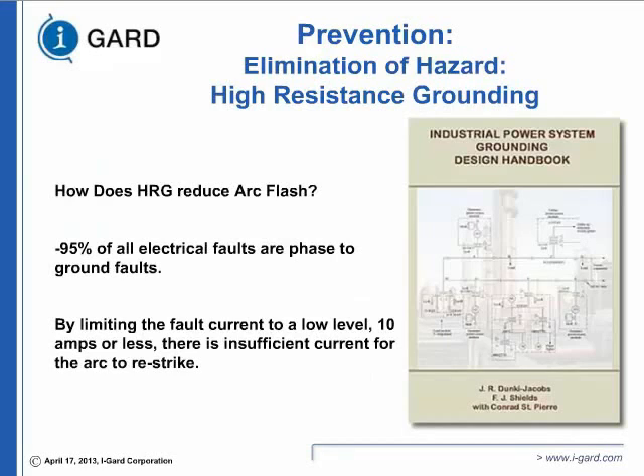How does high resistance grounding reduce arc flash? This is extracted from a book by Dunki-Jacobs, the person who first analyzed or produced a paper on the arcing fault. Up till then everybody was prone to just consider the bolted fault. All your equipment is designed to withstand a bolted fault, and his opinion was, he worked for a very large company which was a leader in the electrical industry, manufacturers, that 95% of all electrical faults are phase to ground faults. They start as phase to ground. Then they escalate to phase to phase. So it stands to reason, if we can prevent them from escalating, we can never prevent the first fault from happening. There could be cable insulation damage, motor damage, but yes, we can prevent the second fault, not allow it to go phase to phase.